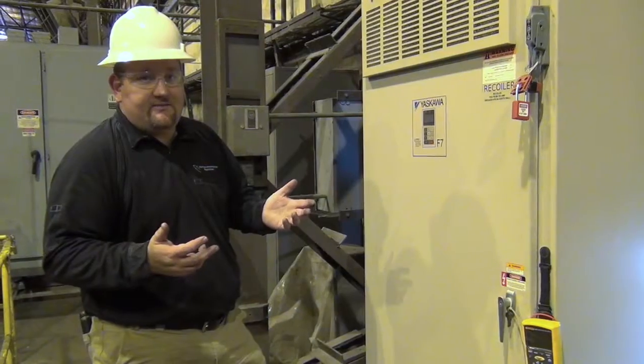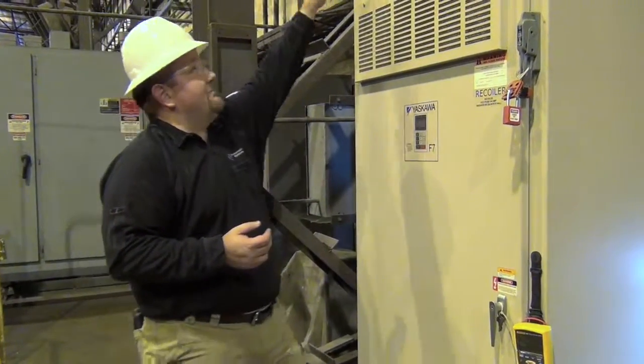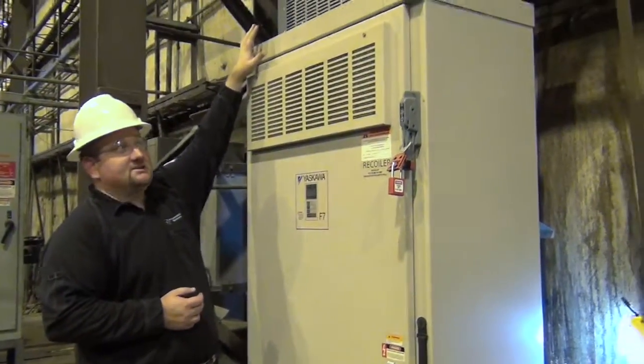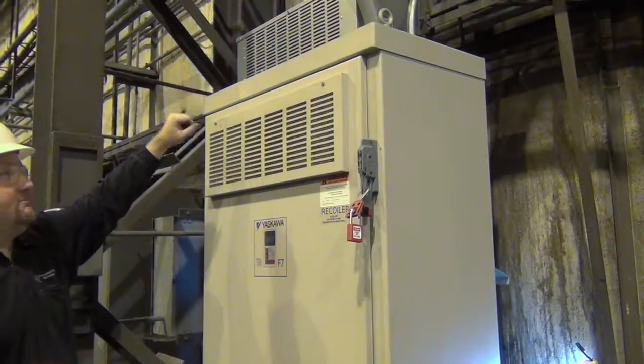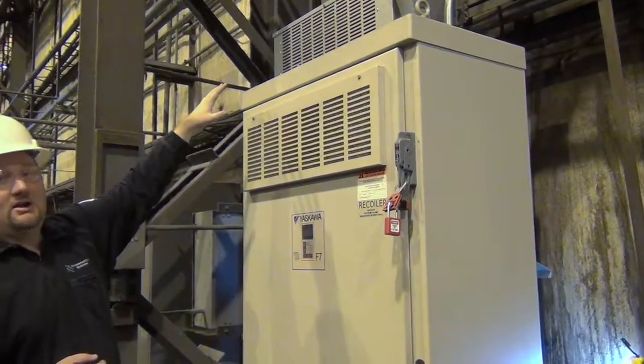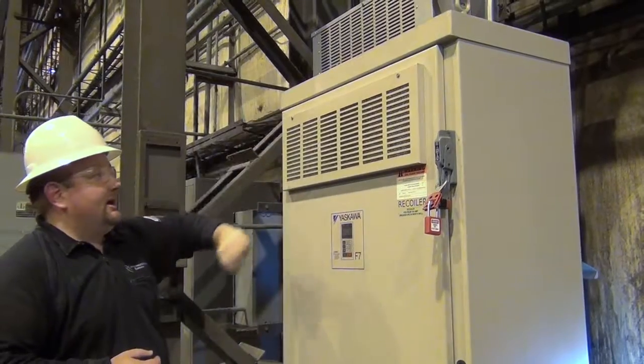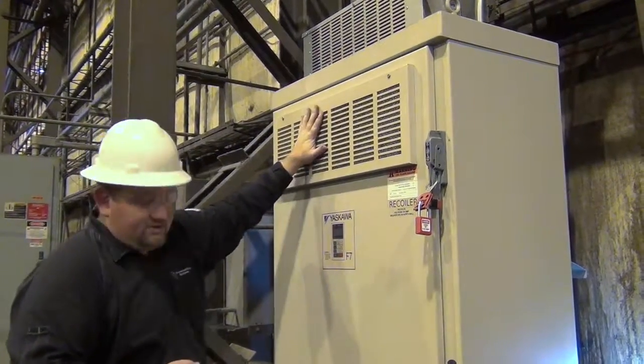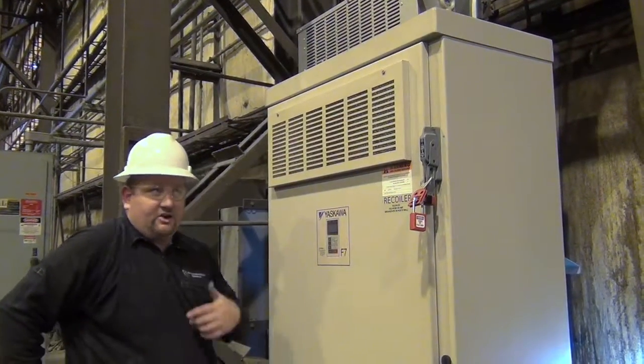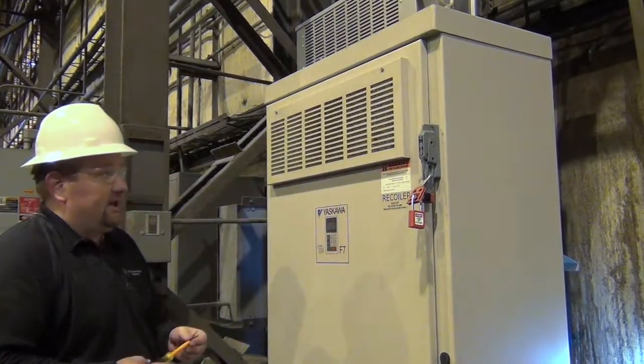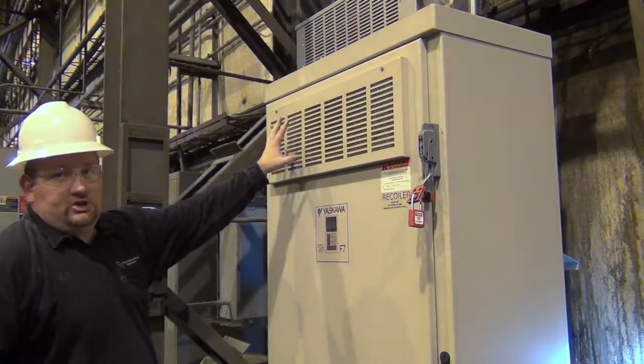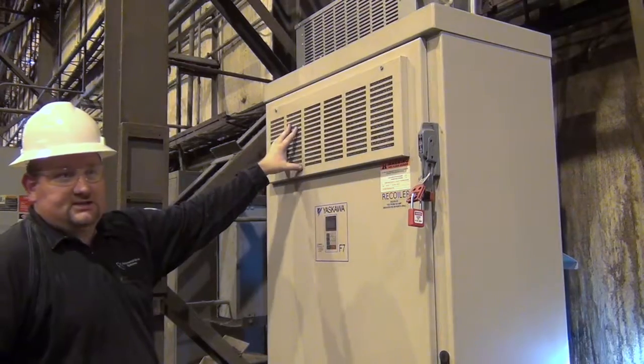The last item that we have on this drive is to clean the top of it. This particular drive has a resistor bank for dynamic braking. So we'll get a ladder, get up there and blow all of the dust out of that. And then we're also going to remove these covers for the fans and get the fan and filter for the cabinet cleaned out as best we can. On these, once they're removed, you can use a higher pressure air to make sure they get as clean as possible.